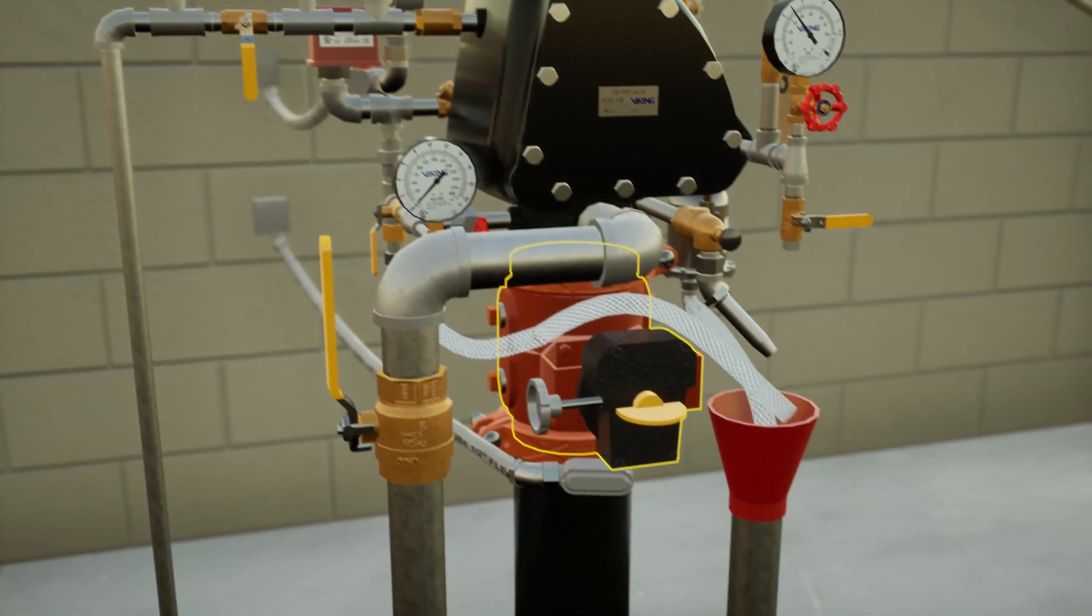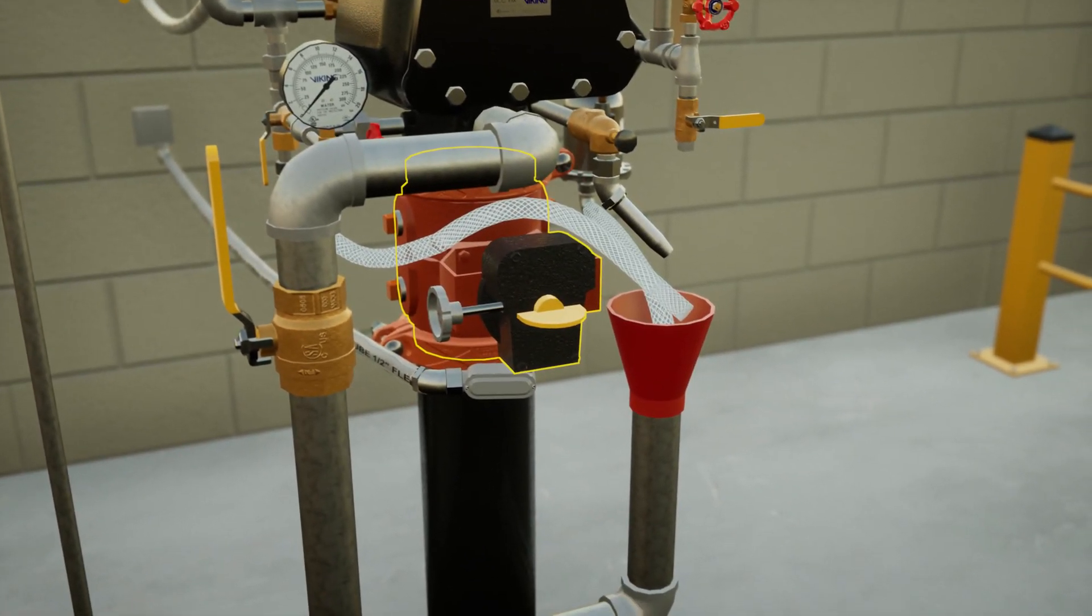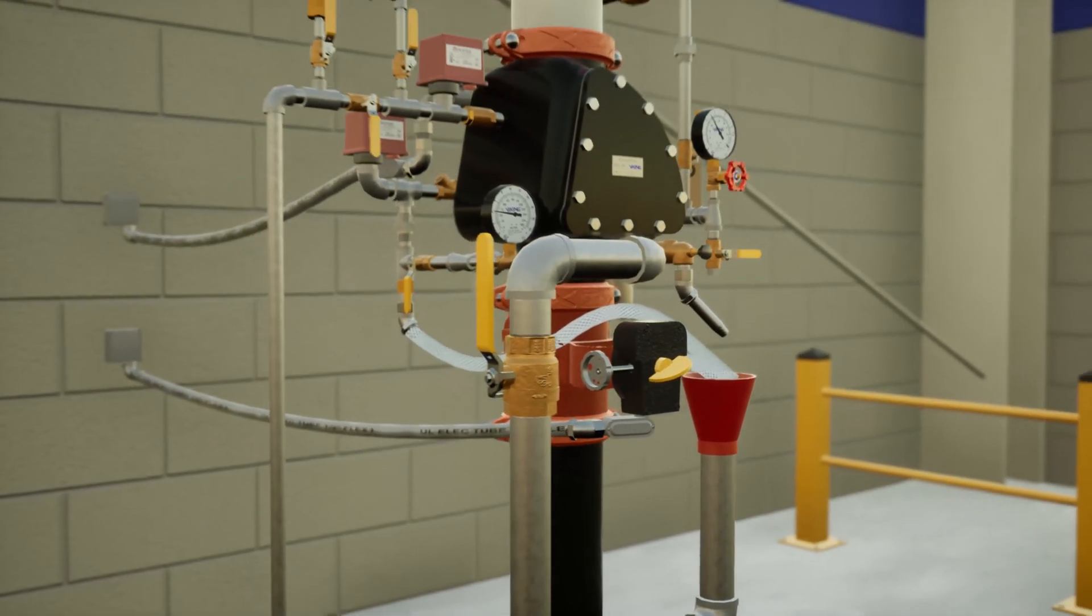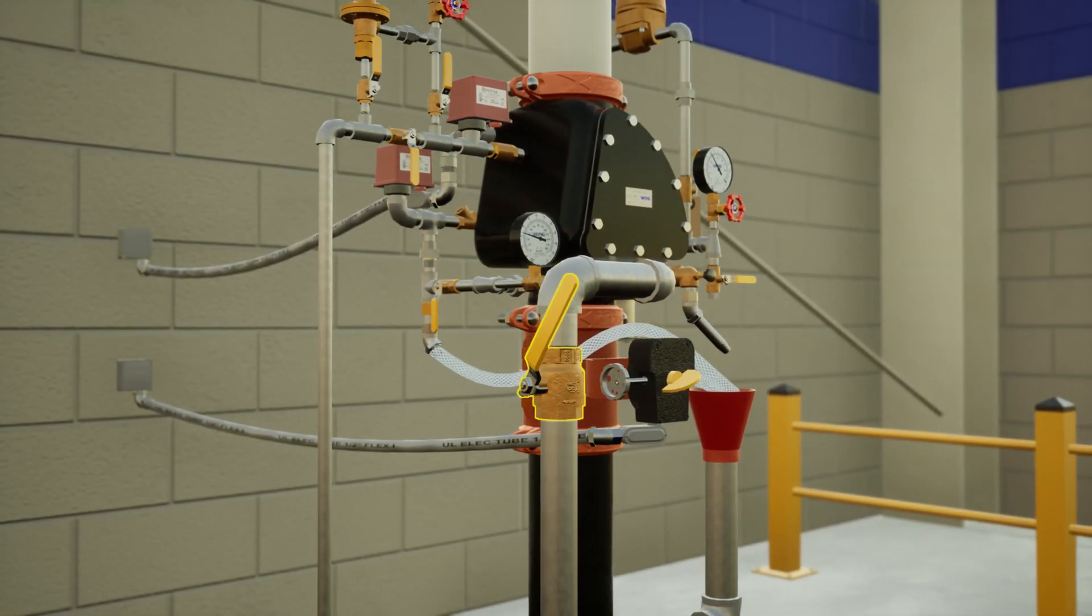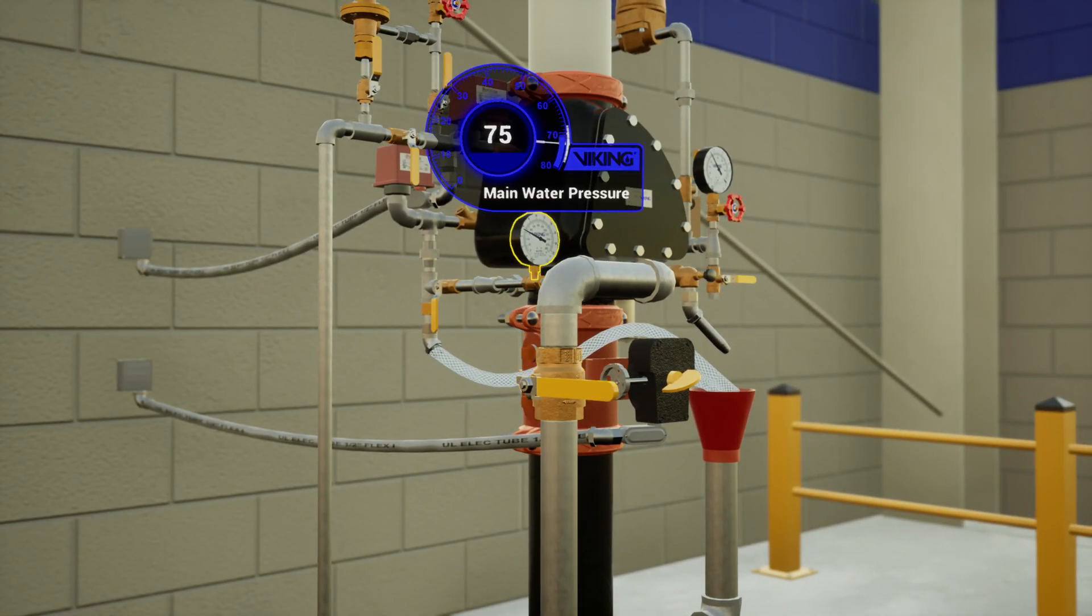Partially open the water supply valve and allow water to enter the inlet of the valve. Now close the main drain. Water supply pressure will show on the water supply pressure gauge.